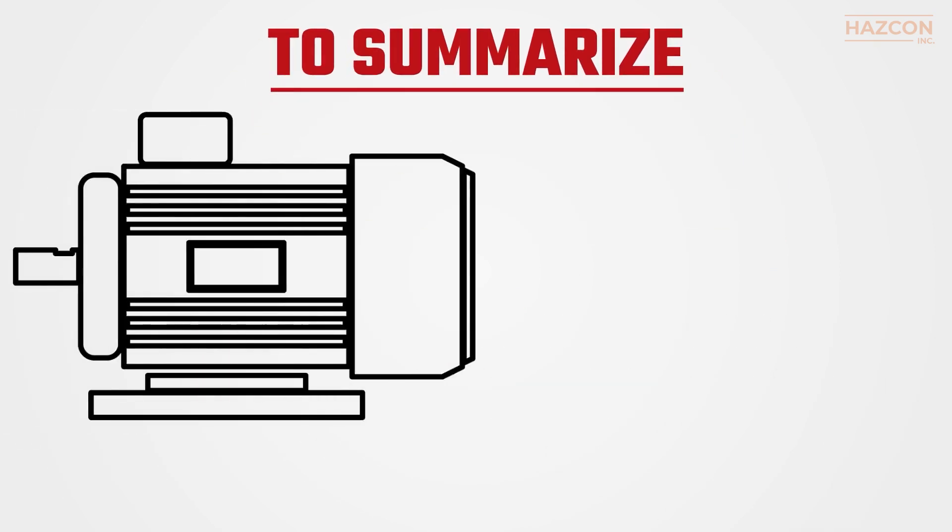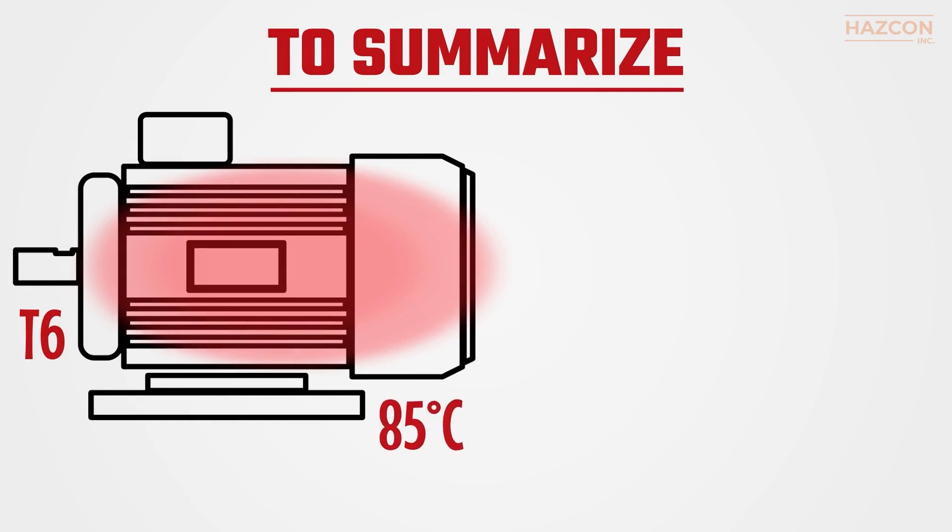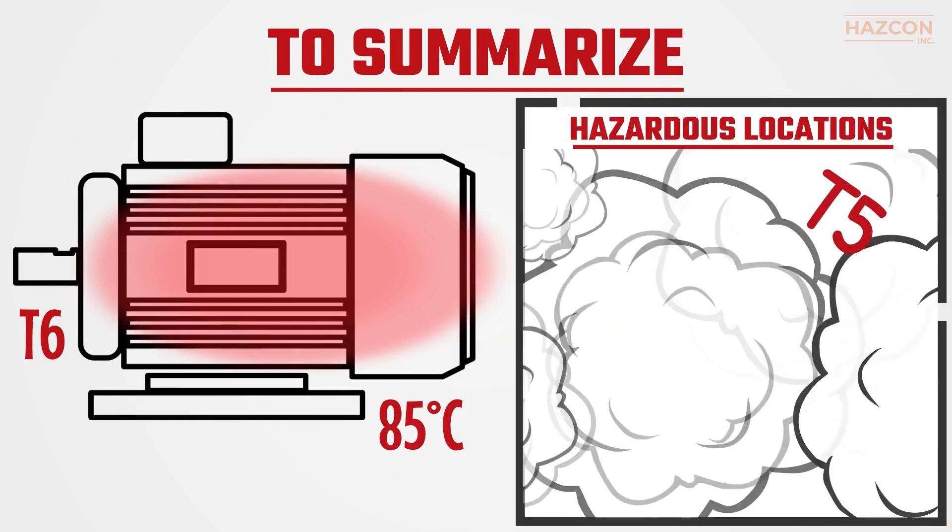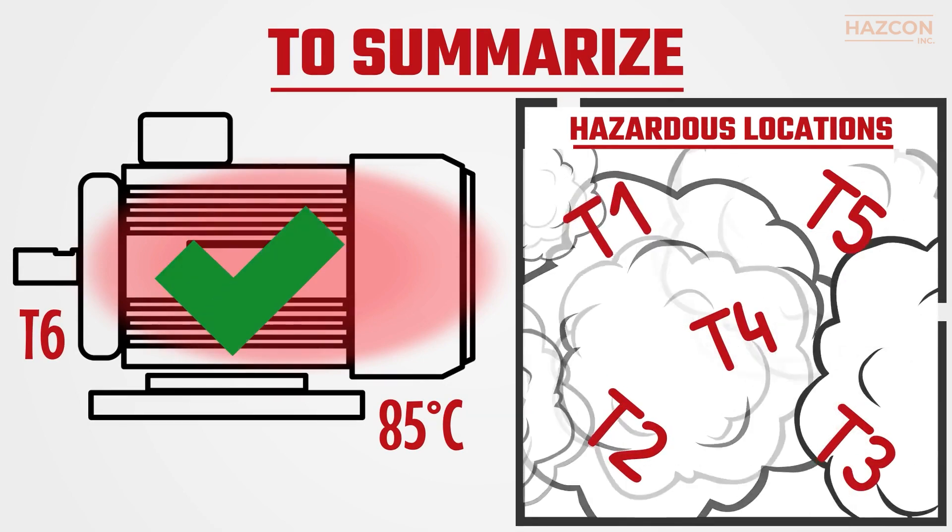All equipment with a T6 rating which has a maximum surface temperature of 85 degrees Celsius, can also be used in T5, T4, T3, T2, and T1 environments.